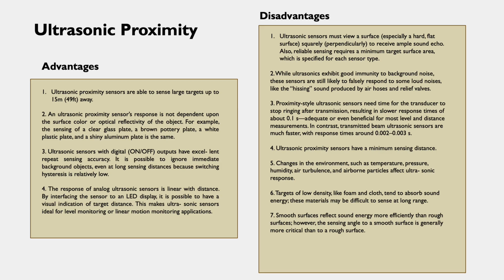Next, proximity style ultrasonic sensors need time for the transducer to stop ringing after transmission, resulting in slower response times of about 0.1 seconds - adequate for most level and distance measurements. In contrast, transmitted beam ultrasonic sensors are much faster, with response times around 0.002 to 0.003 seconds. The faster the sensor, the more output it can produce. Number 4, ultrasonic proximity sensors have a minimum sensing distance.